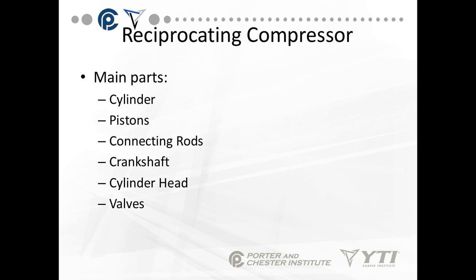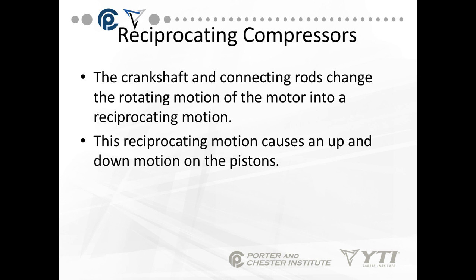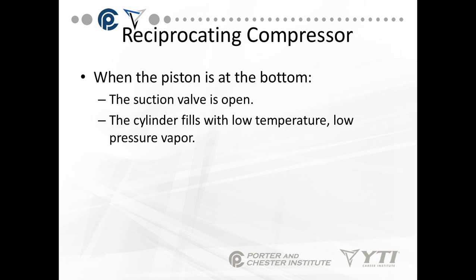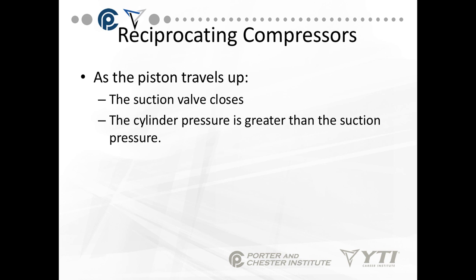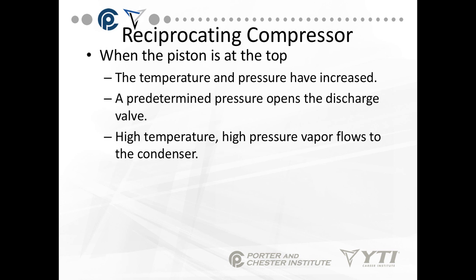The main parts of the reciprocating compressor are: a cylinder, a piston, connecting rods, a crankshaft, a cylinder head, and valves. The crankshaft and connecting rod change the rotating motion of the motor into a reciprocating motion. When the piston is at the bottom of the stroke, the suction valve is open and the cylinder fills with low-temperature, low-pressure vapor. As the piston travels up, the suction valve closes and cylinder pressure becomes greater than suction pressure. When the piston is at the top, temperature and pressure have increased — whenever we compress gas we increase the temperature. A predetermined pressure opens the discharge valve.